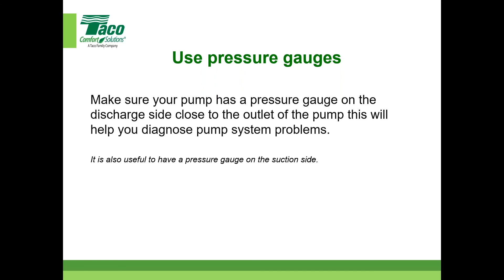Always, if you're going to have flow control, which most of us do, put the valve on the discharge. Don't put a control valve on the suction side. You're going to starve the pump. You're going to cause issues there. All right, never use it on the suction side. VFDs, what is it, 85 to 95% of projects have VFDs. Now, what is it, over 5 horsepower it has to. So keep that in mind.